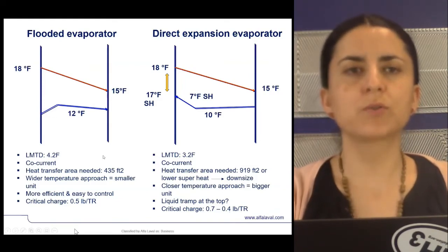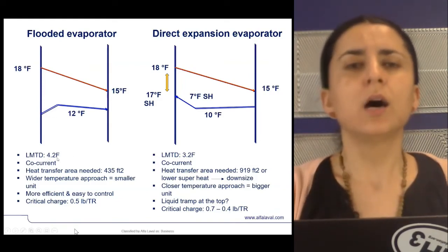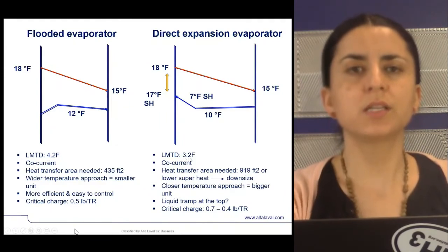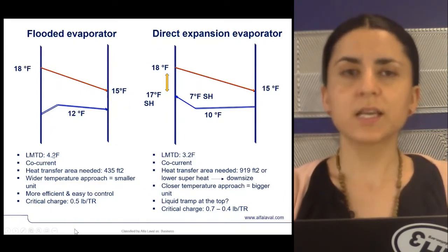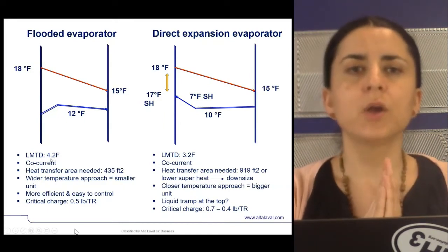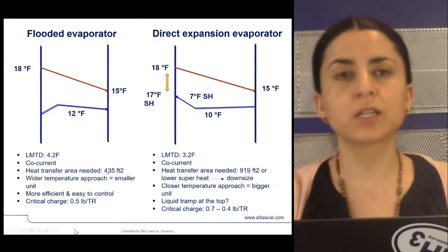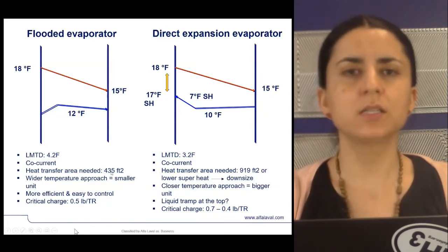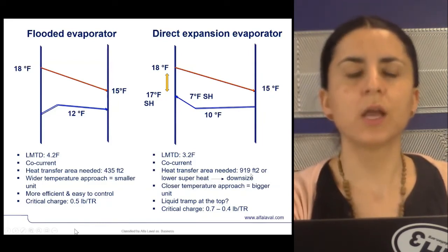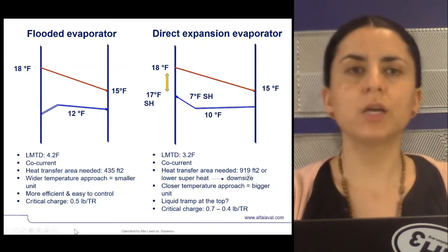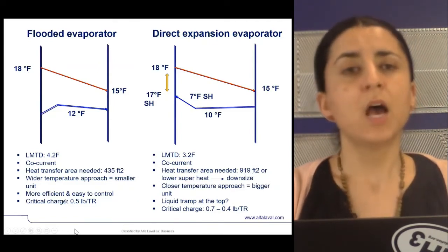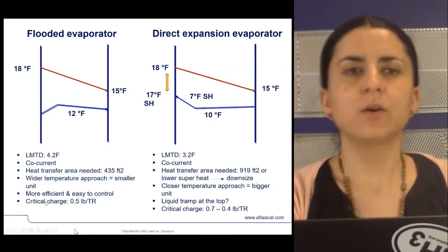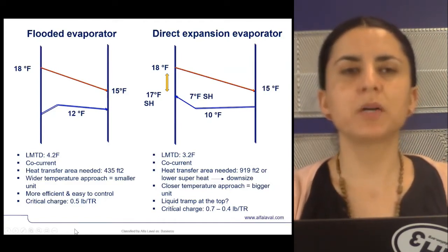LMTD, which is the temperature relationship between inlets and outlets, temperatures dictate the size of the heat exchanger. In this case, with the flooded heat exchanger, we'll need less heat transfer area than direct expansion. This translates into a lower cost of the heat exchanger. However, you have to put a separator on top. An optimized separator can allow us to work efficiently at the highest possible suction and reduce the ammonia charge that can end up being very close to a direct expansion application.